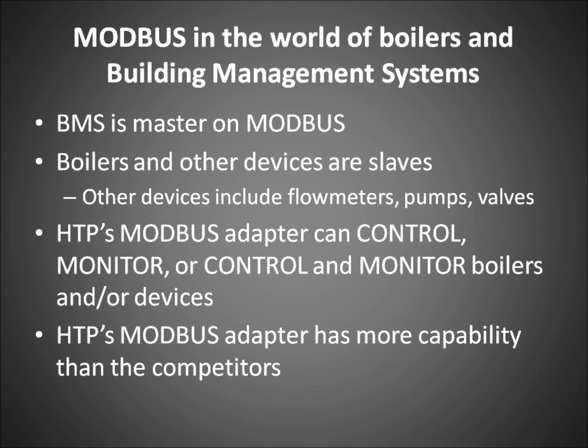All right, continuing, ModBus in a world of boilers and building management systems. The BMS is the master on the ModBus. Boilers and other devices are slaves. Other devices include flow meters, pumps, valves, and others. HTP's ModBus adapter can control, monitor, or control and monitor boilers and/or devices. The HTP ModBus adapter has more capability than the competitors.